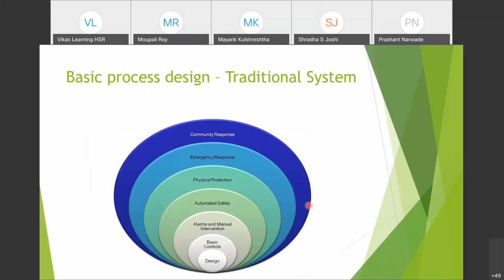Now, if we look at the flow with respect to the BPCS and a safety instrumented system, we have got a basic design and basic control system, which these two circles contribute to the BPCS. Later on, whatever we see here is a part of safety instrumented system: alarms and manual intervention, automated safety, where we have overrides of systems so that the entire system can actually be taken into a safe state. Physical protection of the assets - it could be human assets, it could be resources, it could be the company assets, or it could be environment.